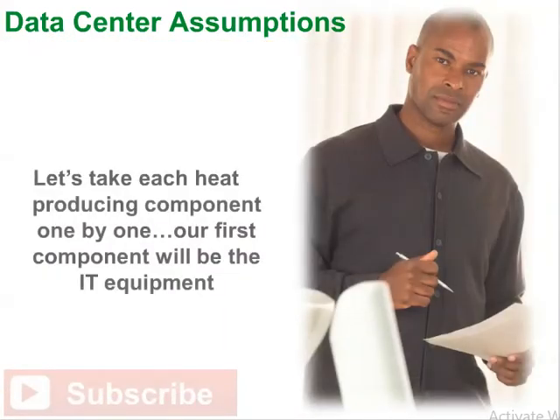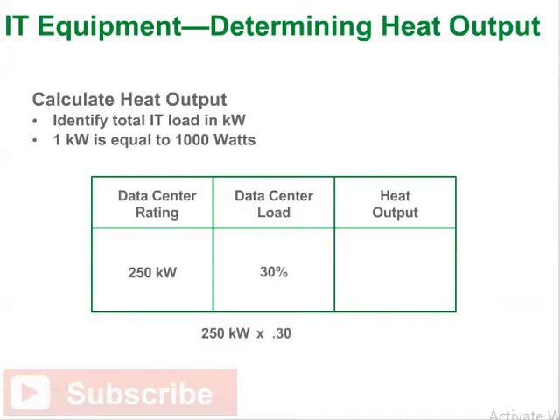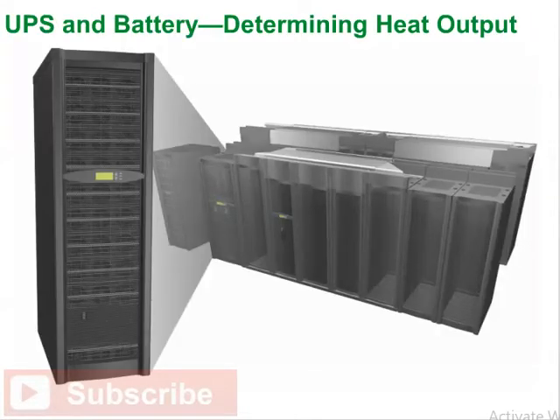Let's take each heat-producing component one by one to work through the heat output calculation worksheet. For IT equipment, we identify our total IT load in kilowatts. Our sample data center is rated at 250 kilowatts, and a kilowatt equals 1,000 watts. Loaded at 30% of capacity, the IT heat output is 75 kilowatts — that is, 250 kilowatts times 0.30. For more information on calculating IT power loads, please consider the DCU course, Calculating Total Power Requirements.